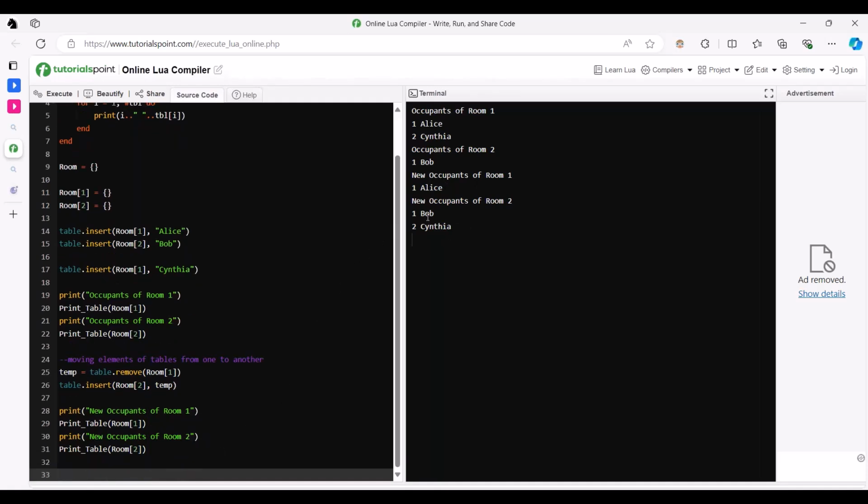So if we went to room 2, we would say we want Bob to do the work first because he's element 1. And when Bob did an operation, he either opened or closed in the case of cap banks, we would remove Bob and add him back to the list at the bottom of the list. So we actually had a dynamic ordering table to identify what the next cap bank should operate in a sequence.